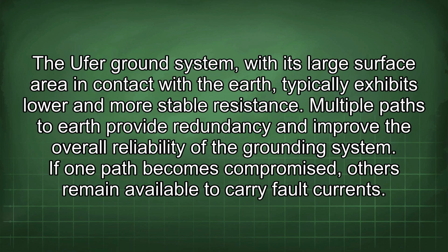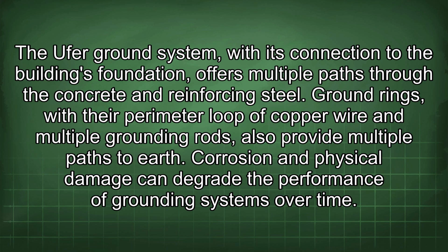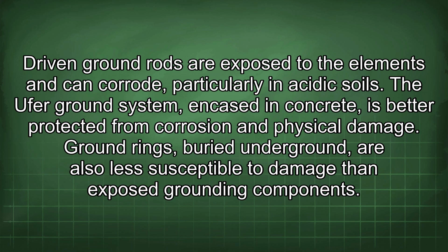If one path becomes compromised, others remain available to carry fault currents. The Ufer ground system, with its connection to the building's foundation, offers multiple paths through the concrete and reinforcing steel. Ground rings, with their perimeter loop of copper wire and multiple grounding rods, also provide multiple paths to earth. Corrosion and physical damage can degrade the performance of grounding systems over time. Driven ground rods are exposed to the elements and can corrode, particularly in acidic soils. The Ufer ground system, encased in concrete, is better protected from corrosion and physical damage. Ground rings buried underground are also less susceptible to damage than exposed grounding components.